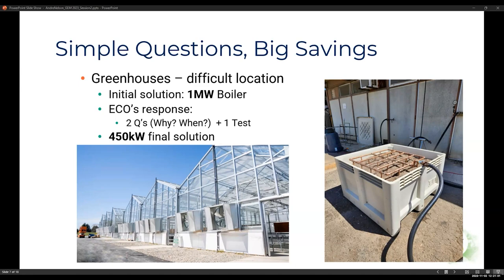The second question we asked was: when? Is the equipment generally actually all on at the same time? Because the boiler was sized as such. The answer was no. Typically only one or two of these pieces of equipment would ever be run at the same time year round due to safety and staff limitations.